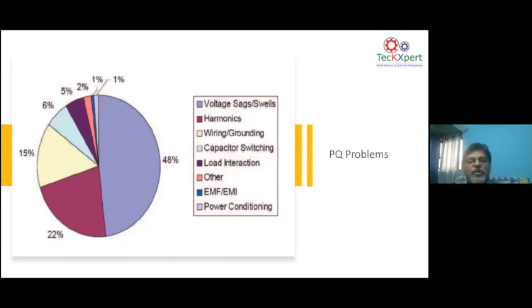Capacitor switching is another power quality problem, as I just said before. Whenever you switch capacitor banks in any grid, naturally it creates oscillatory fluctuations, because a capacitor bank brings in a certain amount of capacitance to the network, which is inductive. So when that LC combination is connected, naturally there is a phenomenon of natural frequency, and at that frequency there's an oscillation. That's why when you do capacitor switching on light loads or full load, under all these conditions, you will have oscillatory transients going over the grid. The other parts are EMI, EMF, because today the majority of power electronic devices produce a lot of electromagnetic interference.